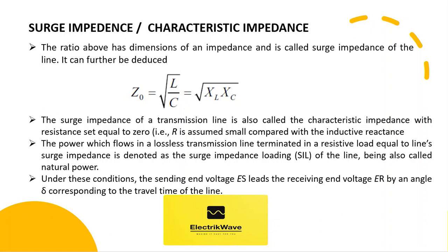The power which flows in a lossless transmission line, terminated in a resistive load equal to the line's surge impedance, is denoted as the surge impedance loading of the line, also called natural power. Under these conditions, the sending end voltage ES leads the receiving end voltage ER by an angle delta, corresponding to the travel time of the line.